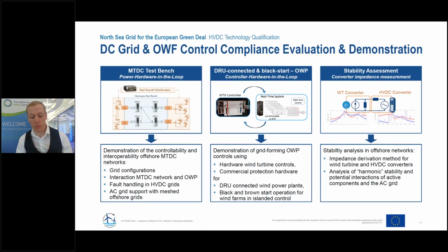As part of this, a fully operational MMC test bench system was created at the premises of RWTH Aachen's existing testing facilities, allowing for power hardware-in-the-loop testing. A number of test cases were carried out using the testing capabilities of this test bench, looking into the crucial interaction between different converter controls and conversion technologies and the protection system, as well as the interaction of meshed HVDC offshore grids with the existing onshore system, with particular emphasis on harmonics. The test cases covered different configurations of multi-terminal setups, offshore wind, and different AC support concepts.